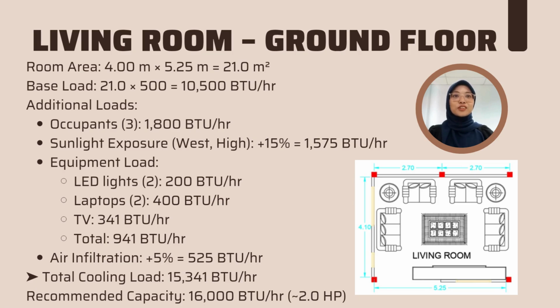Finally, for the living room on the ground floor, the dimensions are 4 meters by 5.25 meters, resulting in 21 square meters and a base cooling load of 10500 BTU. We account for three occupants, which adds 1800 BTU. Due to the west-facing orientation with high exposure and large glass area, we include 1575 BTU from sunlight. For equipment, we consider two LED lights, two laptops, and a television, totaling 941 BTU. Air infiltration contributes 525 BTU.